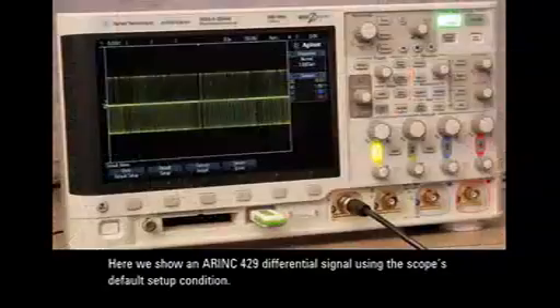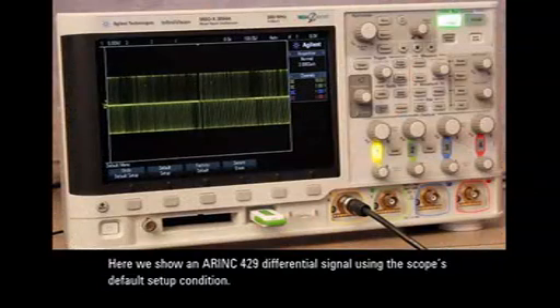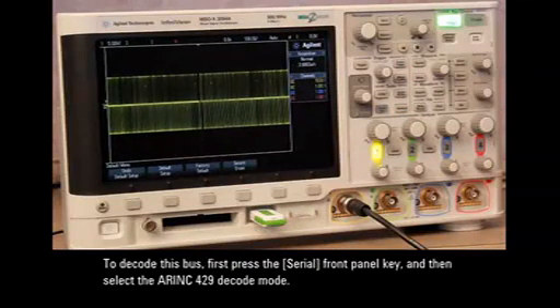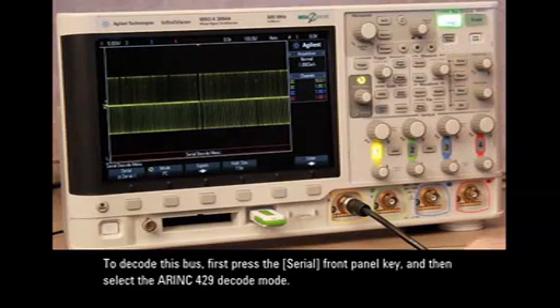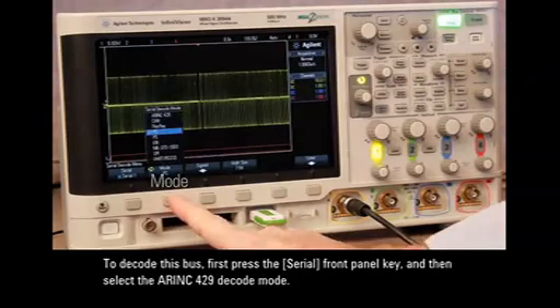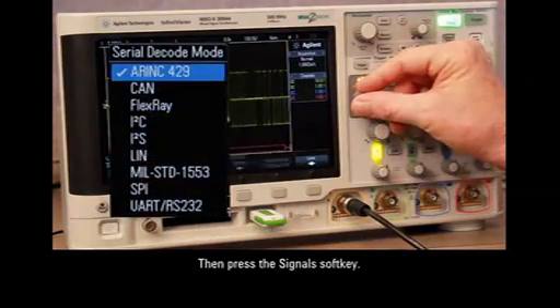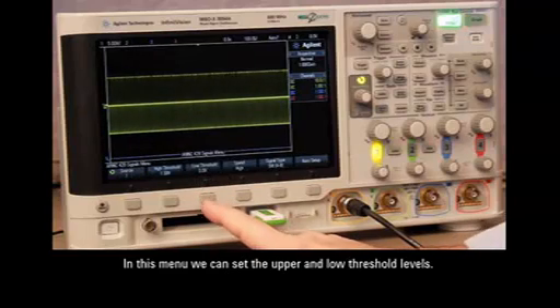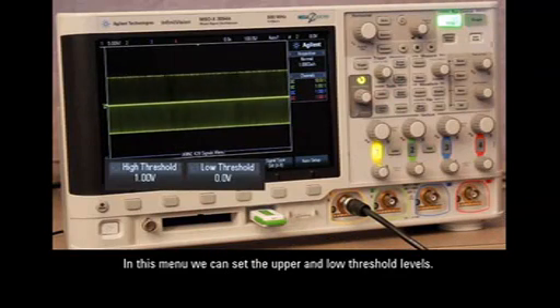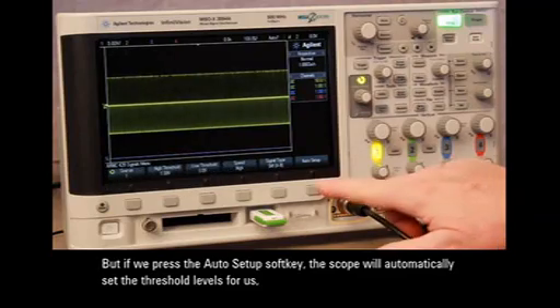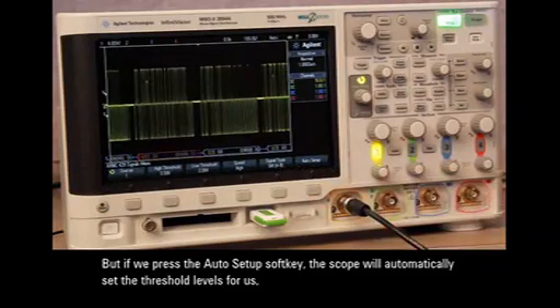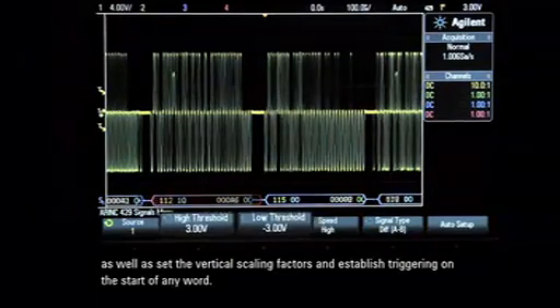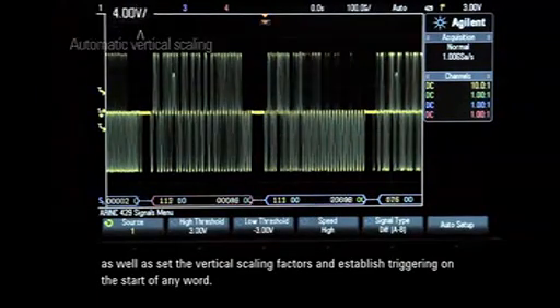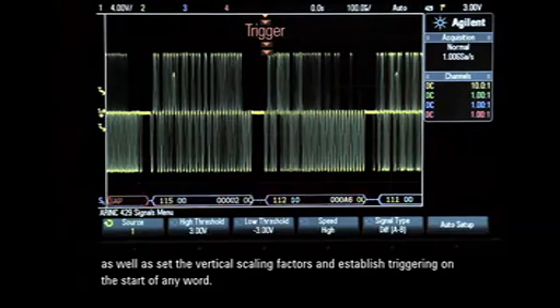Let's begin. Here we show an ARINC 429 differential signal using the scope's default setup condition. To decode this bus, first press the serial front panel key and then select the ARINC 429 decode mode. Then press the signal soft key. In this menu, we can set the upper and lower threshold levels, but if we press the auto setup soft key, the scope will automatically set the threshold levels for us, as well as set the vertical scaling factors and establish triggering on the start of any word.